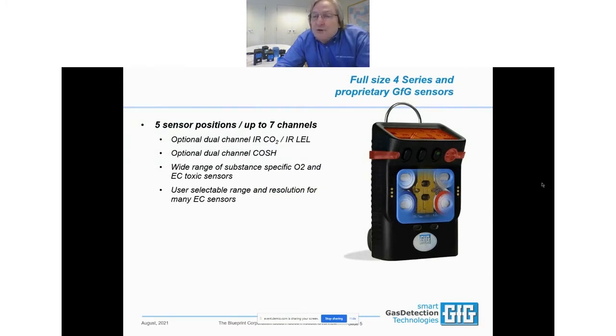Here's a view of the sensors on the inside of the instrument. You can see the central sensor is the patented unique IR sensor, which we use for IR-LEL as well as IR-CO2. If we use a standard catalytic sensor, it fits into the normal sized cylindrical sensor housing that you're used to.